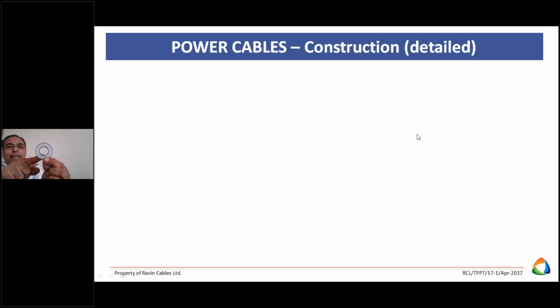Even whatever edges you see here are filled by semiconducting material in the conductor - these sharp edges are filled with the semiconducting material. Now the conductor surface is equipotential. If the conductor surface is not equipotential, it leads to failures. Then comes the insulation part - this white portion is the insulation or dielectric material, which is XLPE - cross-linked polyethylene.